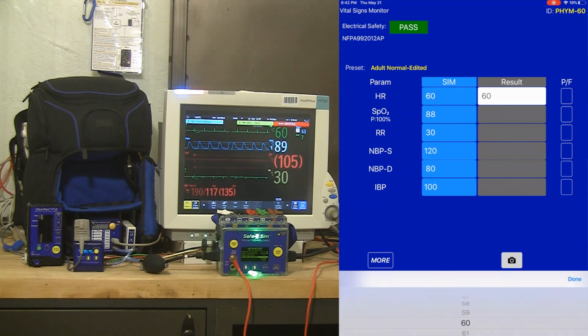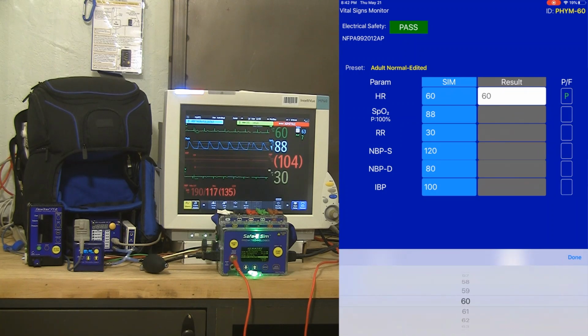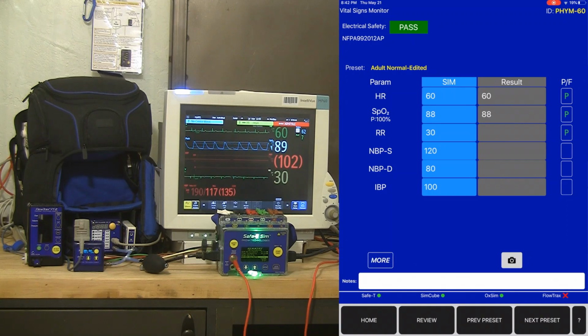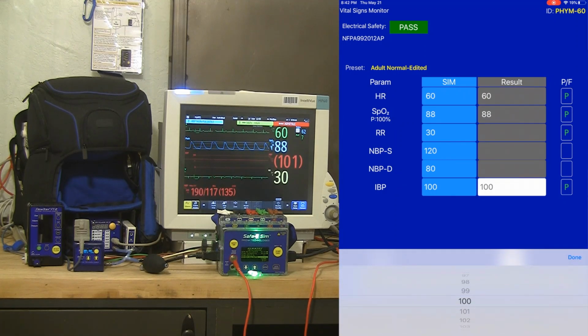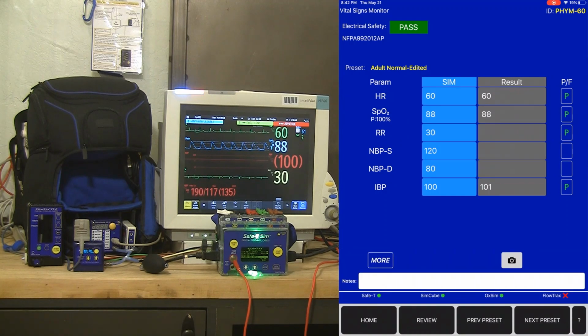So now I've got a result of 60 for my ECG heart rate, 88 for my SpO2, my resp rate is 30. You don't have to put a result in, you can just tap the pass button, but it's very easy to put the result in by tapping on the result box, because we land on the target value and let you scroll quickly to the result.